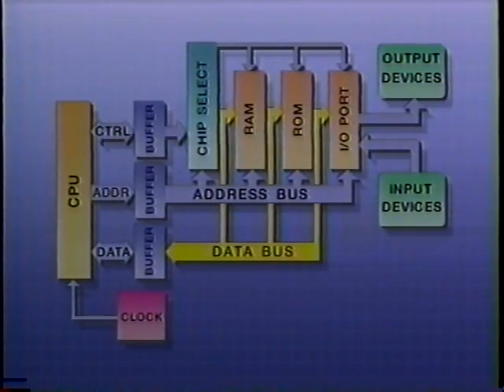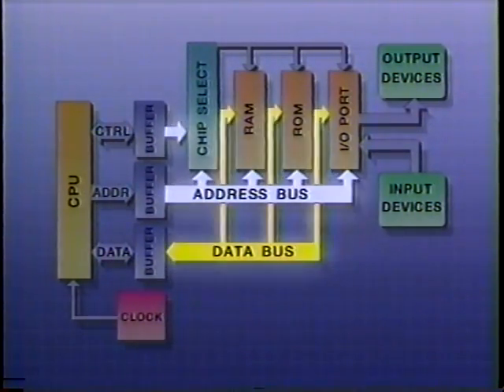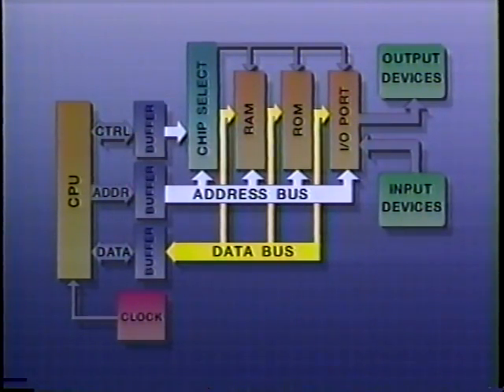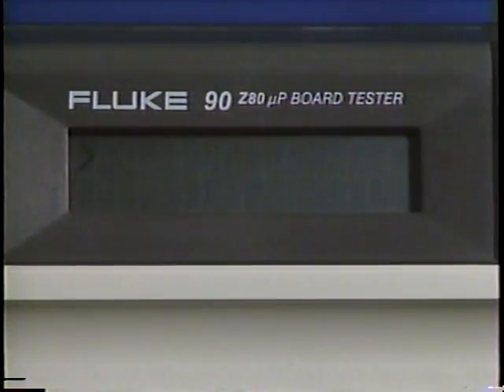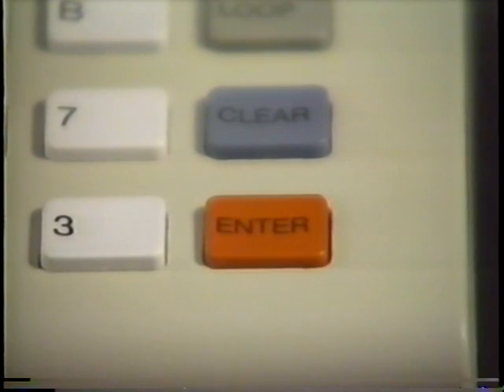The ramp test expands the fault coverage beyond the kernel, allowing you to test all drivers, address decoders, and the integrity of the bus up to the memory and peripheral devices. To execute the ramp test, press the bus test key until Ramp Test is displayed. To run the test, press Enter.